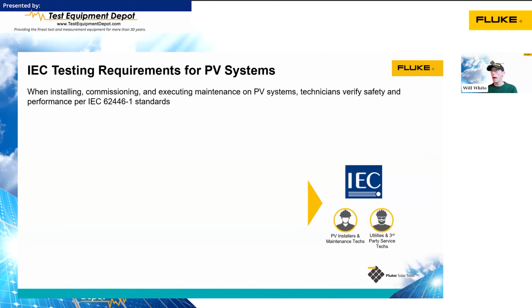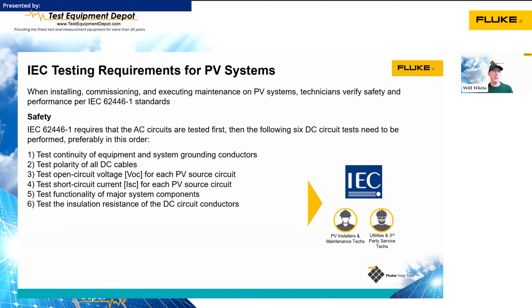Okay, moving on to the IEC standard. IEC 62446-1 is the standard for testing grid-connected photovoltaic systems. It is used predominantly in Europe. It's a requirement to test to this standard when you're installing or maintaining the system in Europe. Here in the US, it's not required, but it's a really good standard to use as a guideline. In this standard, there are two categories of tests. There are safety tests and performance tests.